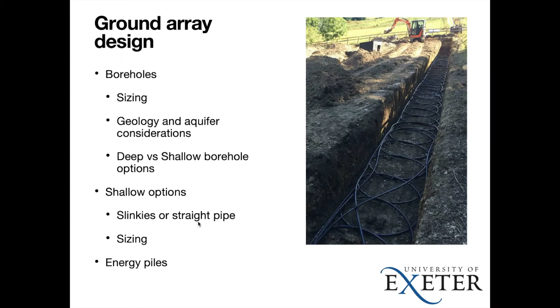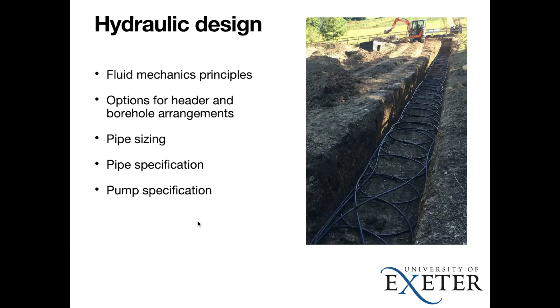Another area where we've seen poor demonstrations is the hydraulic design, correctly sizing the pipework to the ground array, which can lead to poor conductivity with the ground, or oversized pumps circulating around. We've seen examples where the COP of the heat pump has really been compromised by over-specifying the pump for the ground array side.